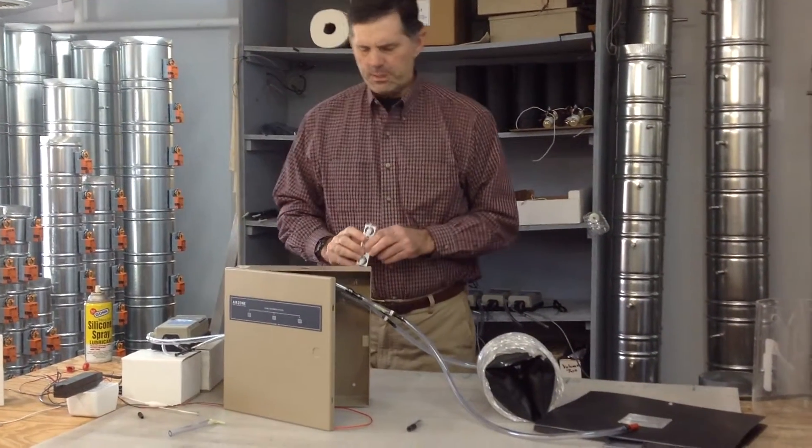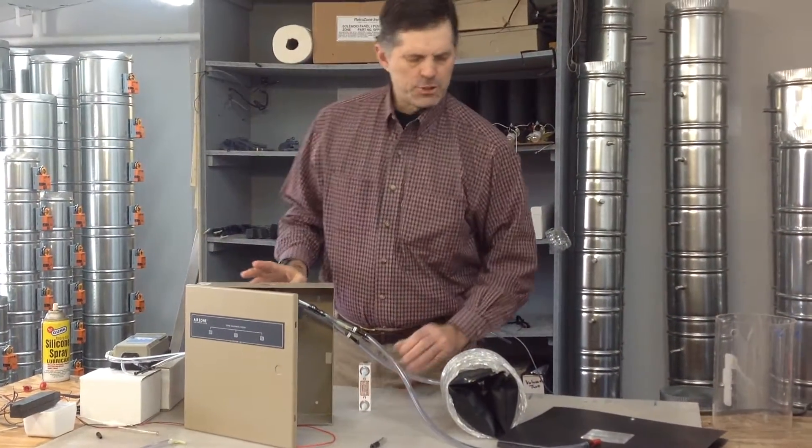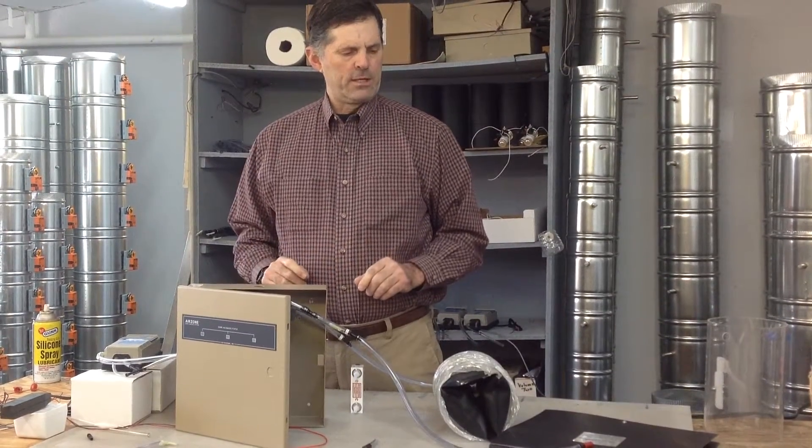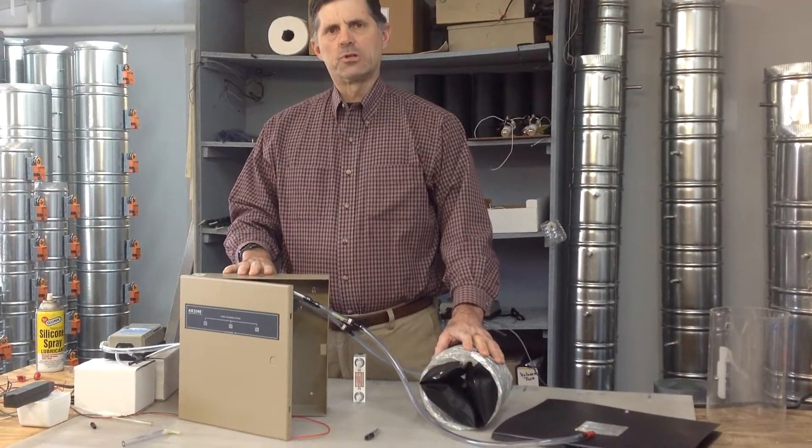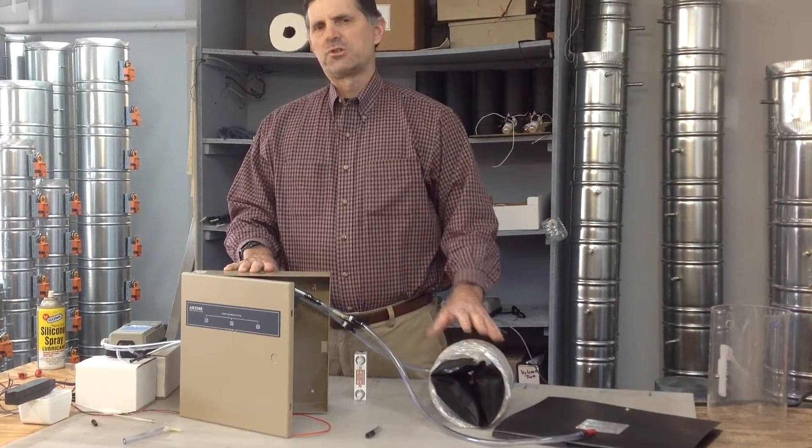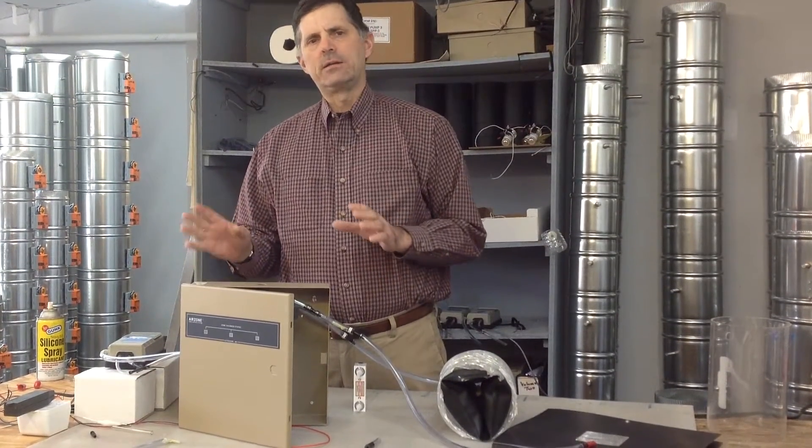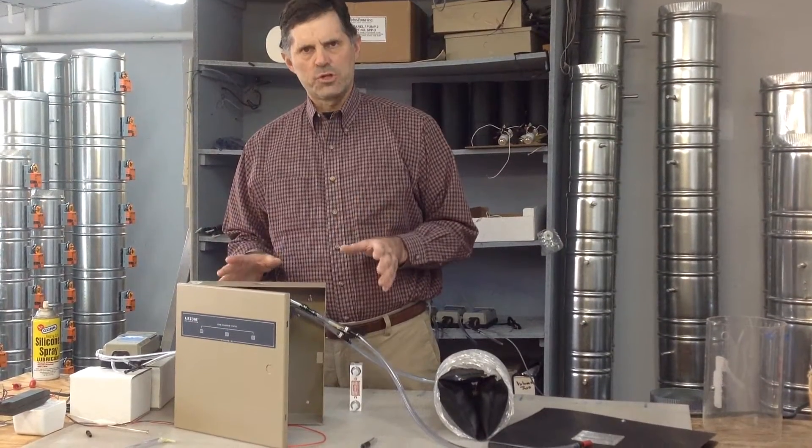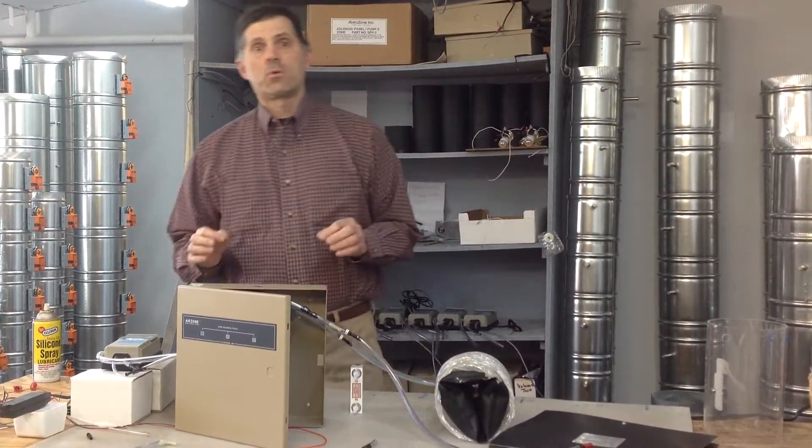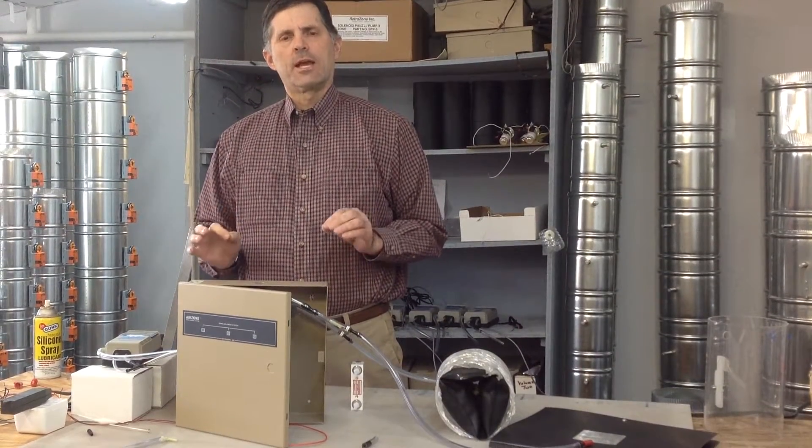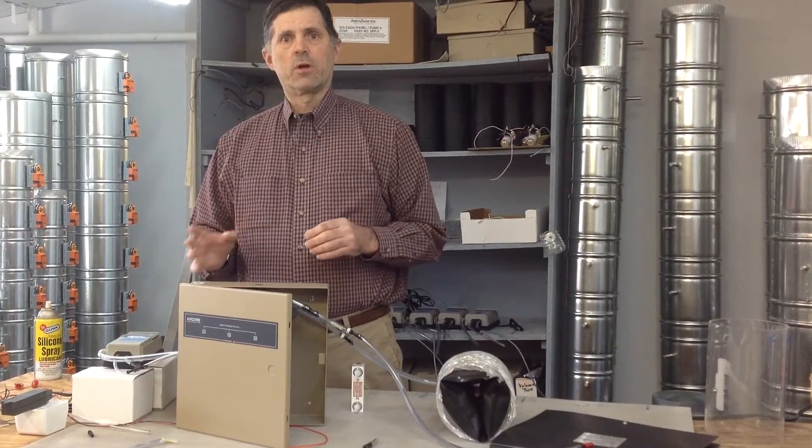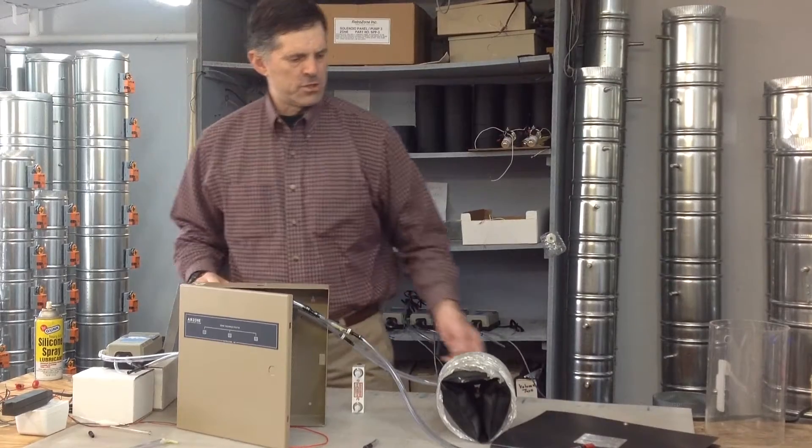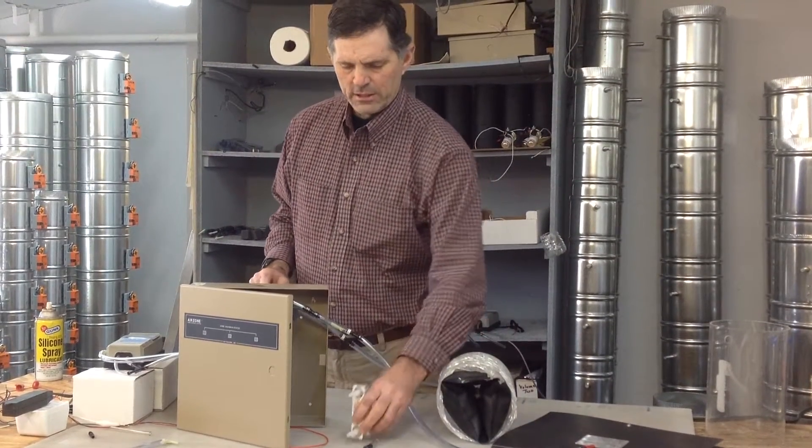That's where I would say a great majority of the problems are going to be. Right there, pumps are easy to replace. They're relatively inexpensive. So, most times that you encounter a system and it doesn't seem to be working right, that's what it's going to be. Now, again, this system was sold under the name InnerZone or InnerZone Systems Corporation starting in about 1986 all the way to 1999. After 1999, same system under the name of RetroZone or RetroZone Inc. Website is RetroZone.com. If you will look under technical resources, you will find various videos and other aids in terms of hooking pumps up and that sort of thing. So, I want to make sure we mention that. These systems are still completely serviceable.